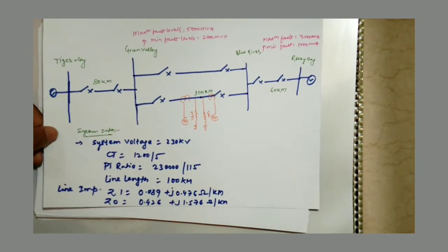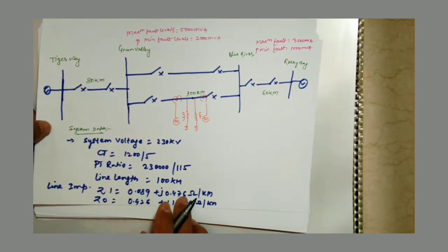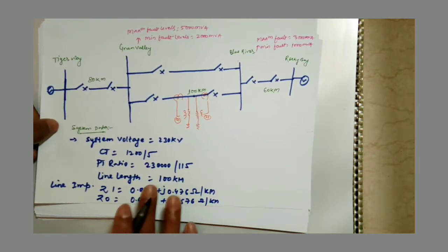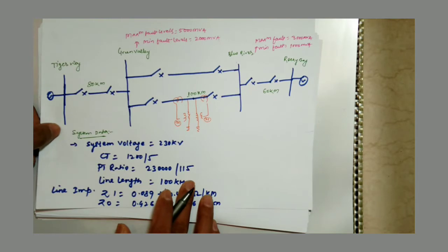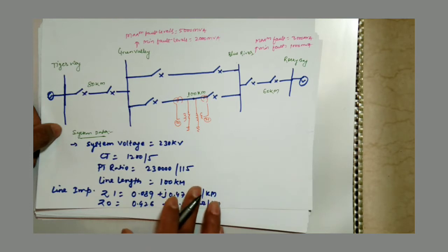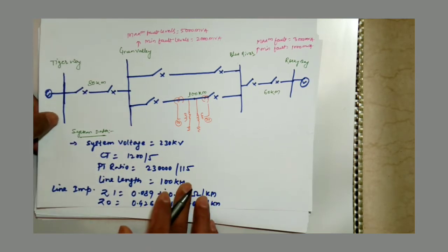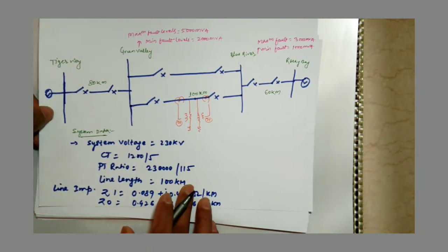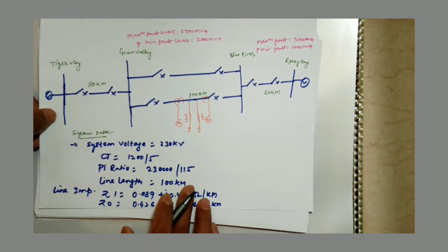We have another zone 4 setting. Zone 4 is used to provide a reverse directional decision for a blocking or permissive overreach scheme. So it must be set further behind the relay than zone 2 for the remote relay. So how will we achieve this setting?